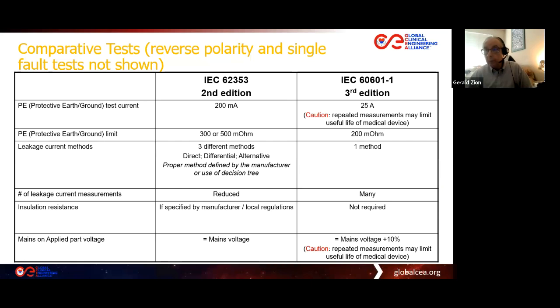Okay, here are some of the comparative tests between the IEC 62353 and the IEC 60601-1 3rd edition. The two tests that could tend to shorten the useful life of the medical device are the protective earth resistance test, that is a 25 ampere application test, and also the mains on applied part or isolation test, and that is done at 110% of mains. Those two tests may tend to shorten the useful life of the medical device, which is why for repeated testing, we are instructed to use the IEC 62353.